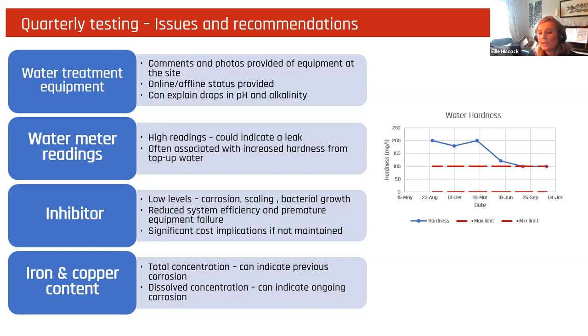And the final point on this is that we found trend analysis really useful, especially where we've had previous corrosion problems, and an individual result has flagged as slightly outside of the limit, but we've monitored over a period of time that it's a negative trend. We've been able to confirm with our water specialist that there is no ongoing corrosion. So we've had really good engagement from that. And thanks.